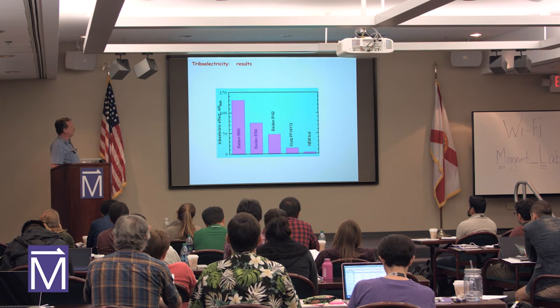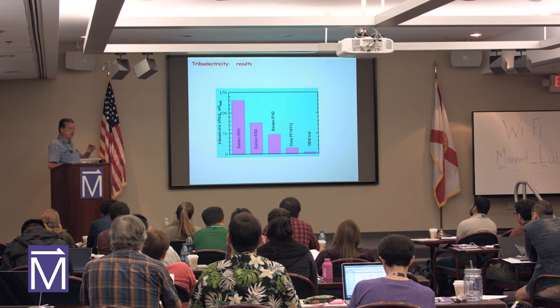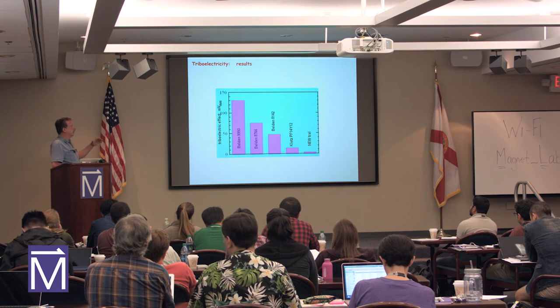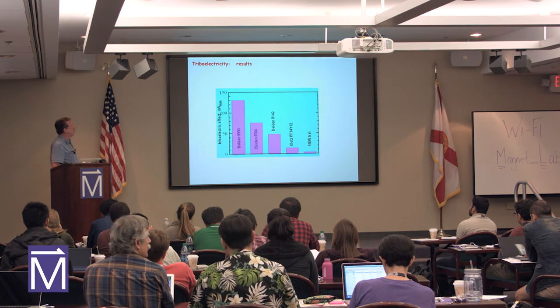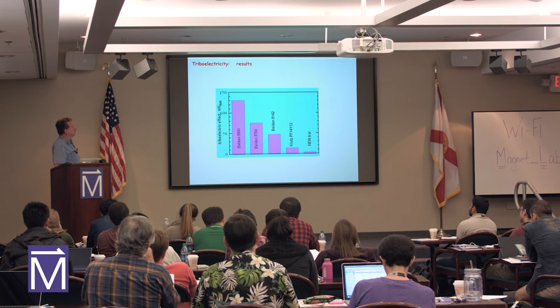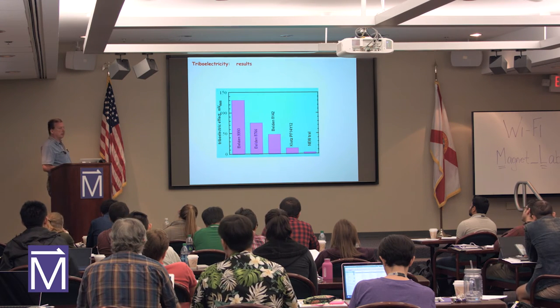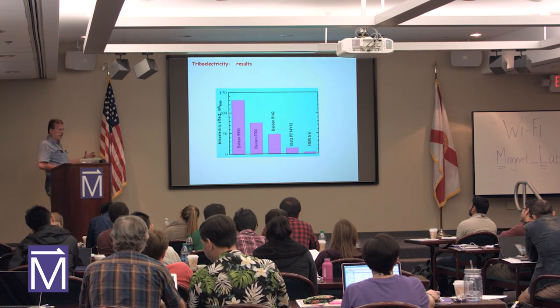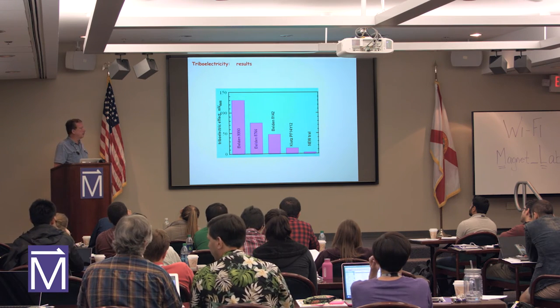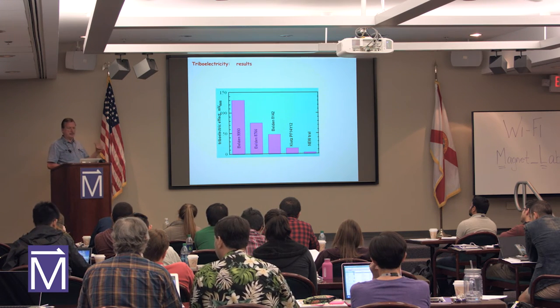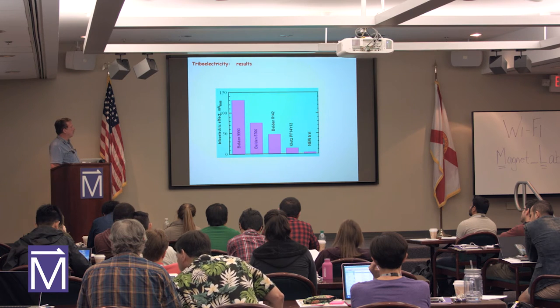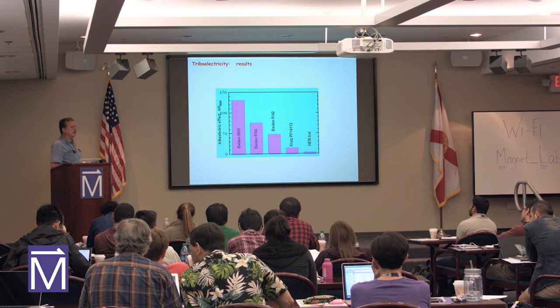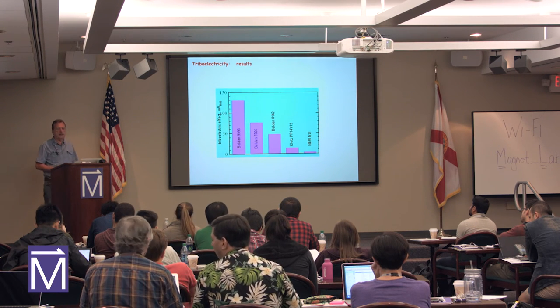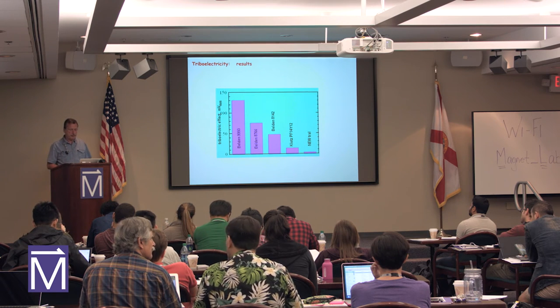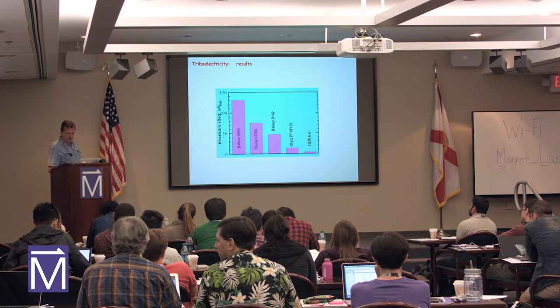They are actually, as Matt mentioned, made with some graphite to conduct between the insulating parts, which makes a little bit of a problem because it's very difficult to connect them. Because on one side you want to isolate, or if this graphite goes between your wires and so on, you cannot have enough resistance to measure high resistive samples.